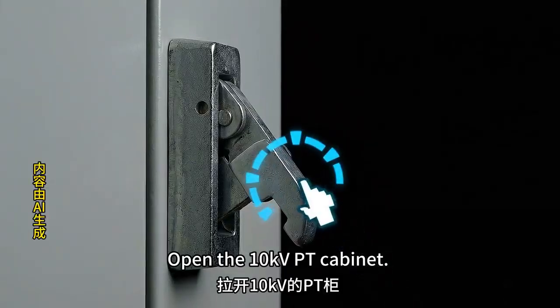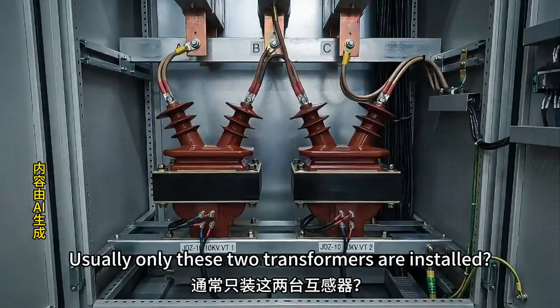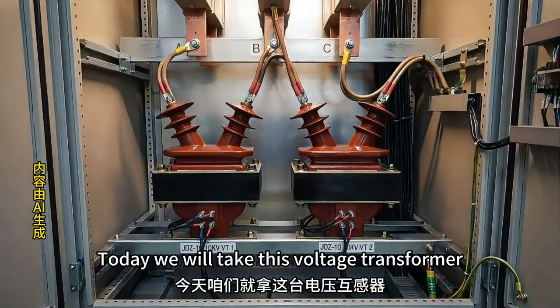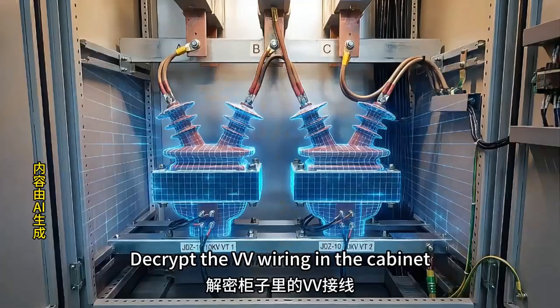Open the 10 kV PT cabinet. Have you ever thought about a question? Why is there a 3-phase high voltage system, yet usually only these two transformers are installed? Today we will take this voltage transformer and decrypt the VV wiring in the cabinet.